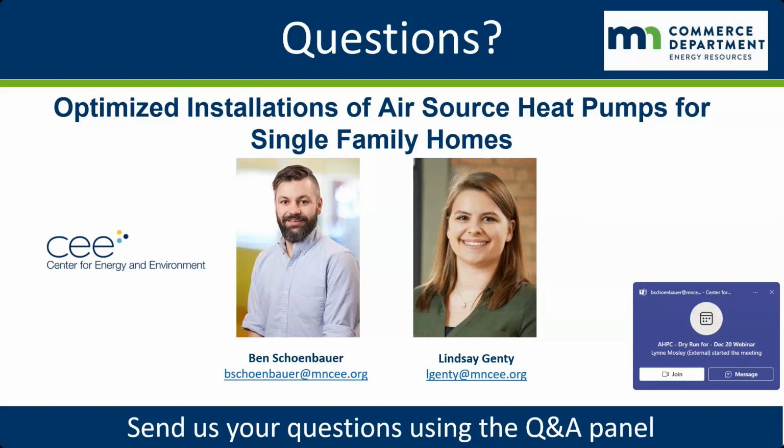That's a lot more accurate way of determining how much heat your house actually uses than things like Manual J or other sizing estimates. I will point out that you probably do want to have some capacity higher than your actual usage to do things like recover from setback, or if it gets really cold over a short period of time, you might want to be able to deliver a little bit higher capacity than what your house actually needs, just to cover some of that changing variation of field work. But yeah, that would be a good way to size your heat pump.